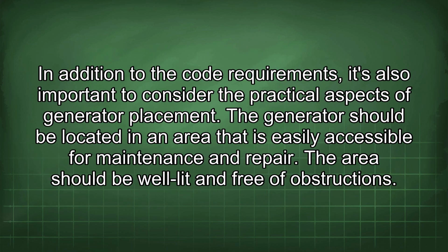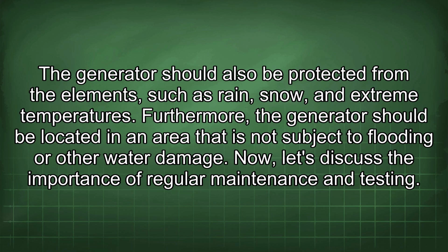In addition to the code requirements, it's also important to consider the practical aspects of generator placement. The generator should be located in an area that is easily accessible for maintenance and repair. The area should be well lit and free of obstructions. The generator should also be protected from the elements such as rain, snow, and extreme temperatures. Furthermore, the generator should be located in an area that is not subject to flooding or other water damage.